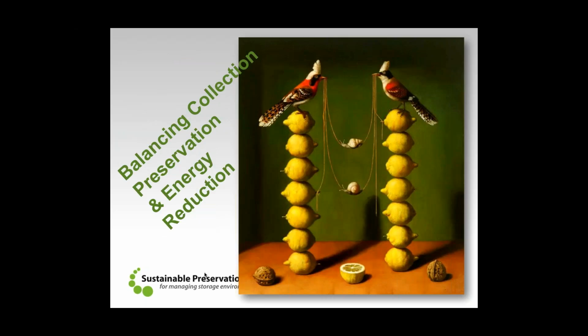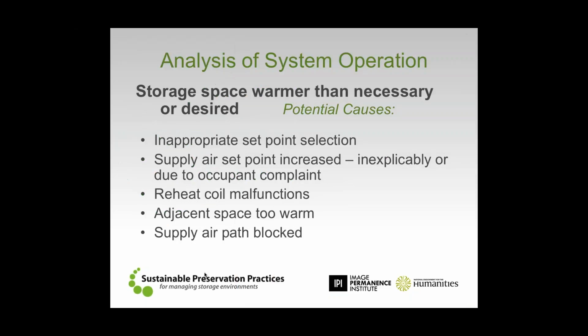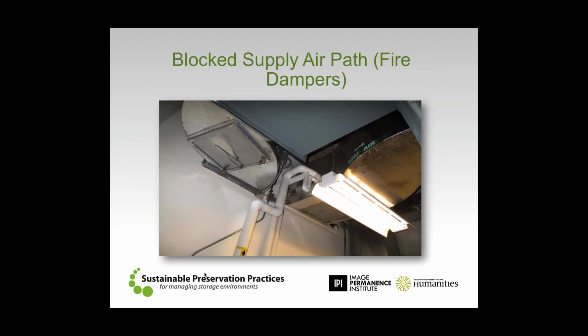Now, balancing that preservation and energy reduction, when we start going through and thinking about the symptom that we see, if we're looking at a storage space, is it warmer than what we need? We want to go through and check, well, is the set point correct? What is the supply air set point, making sure that that's appropriate? Did the reheat coil just go haywire? Is it making the air too hot? Is there heat coming in from an adjacent space? Or, in this particular case, do we have a blocked supply air path?